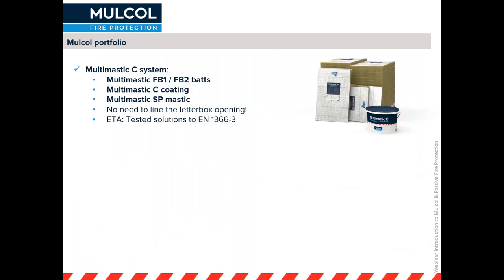The Multimastic C system, which is a coated board system or a batt and mastic system, comes with two different types of boards, the FB1 and the FB2. The FB1 is 50 millimeters and coated on one side only, whilst FB2 is 60 millimeters and coated on both sides of the board. It also comes with the Multimastic C coating and the Multimastic SP.